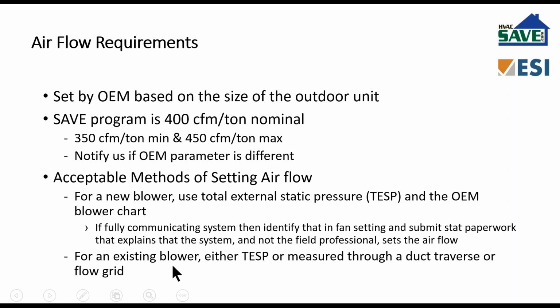Now, for an existing blower, you can use either the measured total external static pressure, or you actually can measure CFM, the airflow itself, through a duct traverse or a flow grid. These latter two are more accurate, they're more convenient, they're certainly recommended, but you need to make sure you have that tool in your truck at that time. Thus, if you don't, you can still refer back to the blower charts.